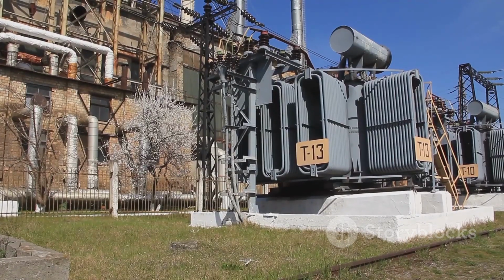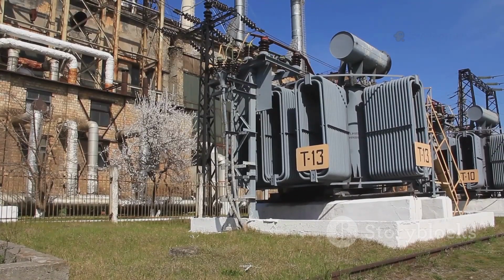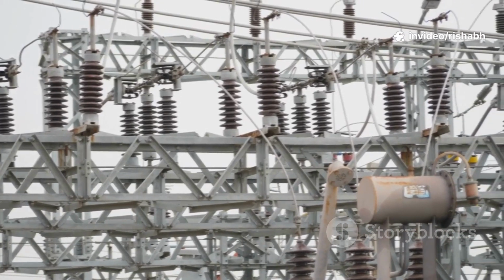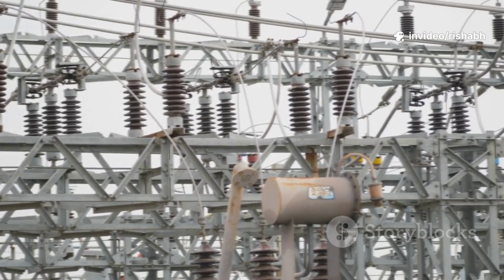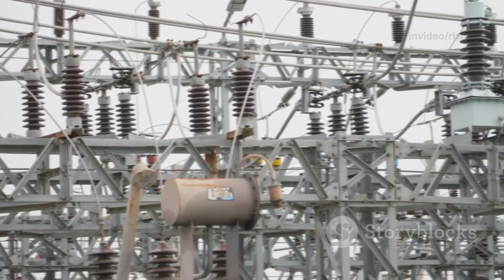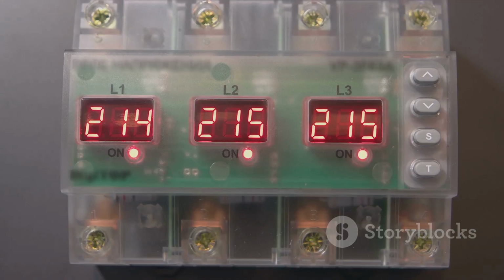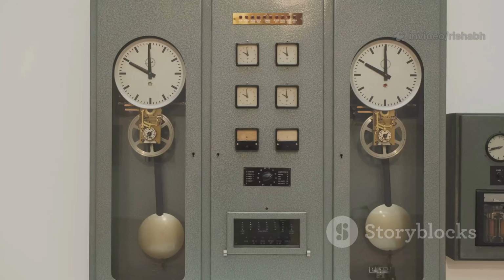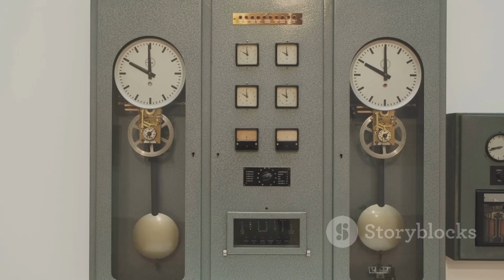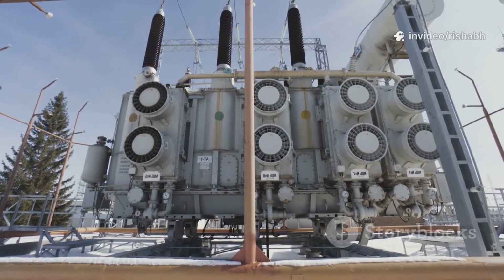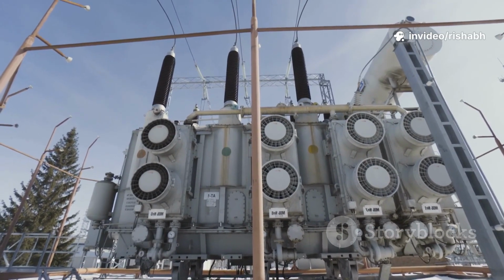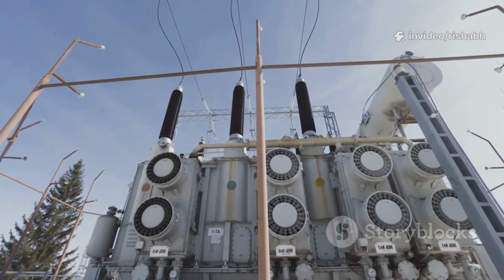The 30-degree phase shift is also crucial for parallel operation. To connect two transformers in parallel, they must have the same voltage ratio, impedance, and critically, the same vector group. If you try to connect a Dyn11 transformer in parallel with a Dyn1 transformer, even though their winding connections are similar, their phase shifts are different. The low voltage of the Dyn1 would be at 1 o'clock, while the Dyn11 is at 11 o'clock. This creates a massive 60-degree phase difference between their secondary terminals, leading to a large circulating current that would damage or destroy the transformers.